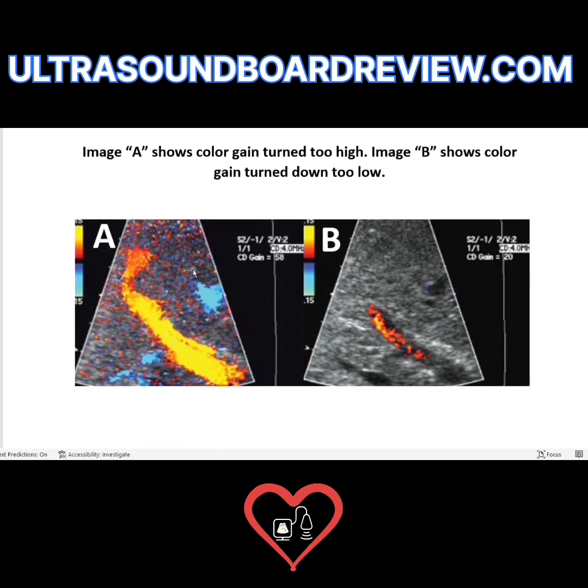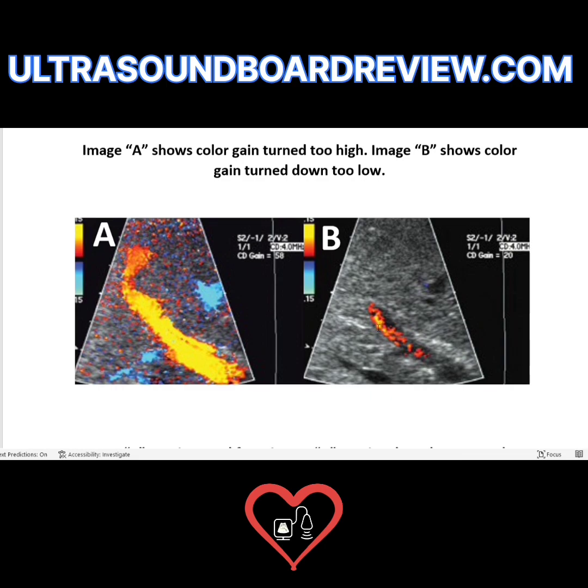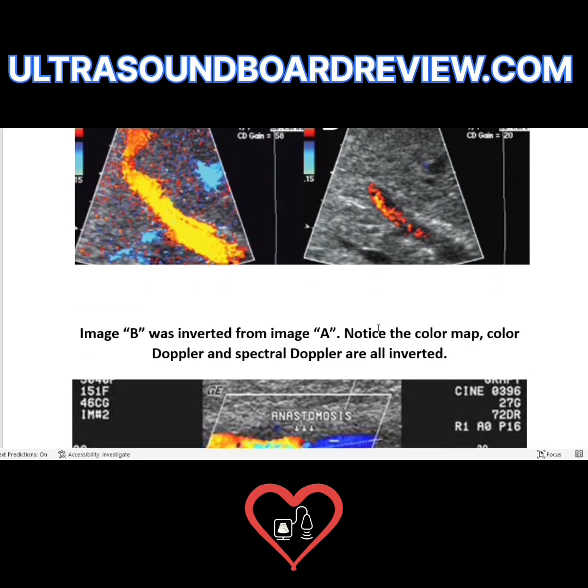In image A, the color gain is too high — you've got color confetti, looks like there's a big party going on. In image B, it's turned down way too low. What you want is a happy medium in between to show color Doppler flowing in the vessel.